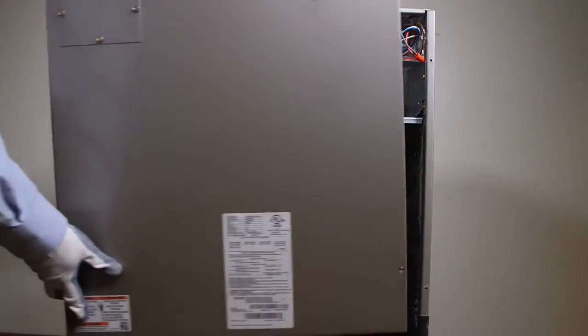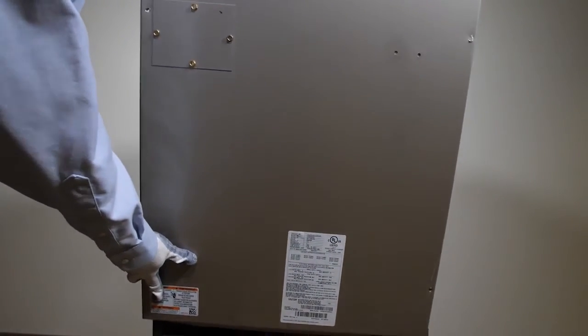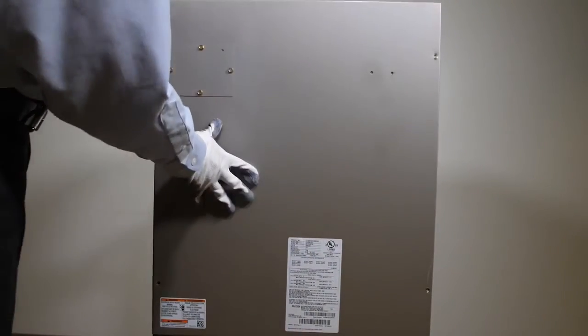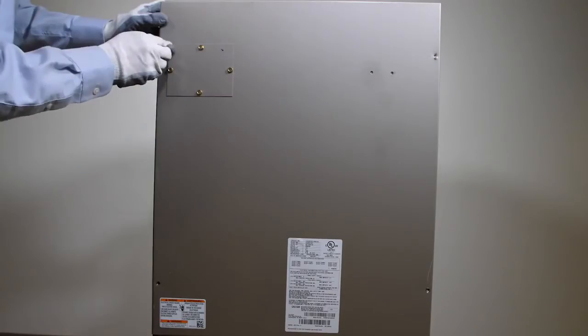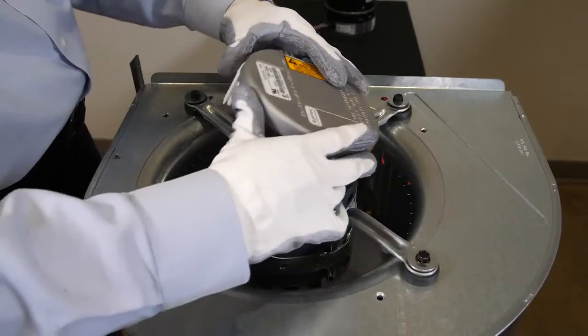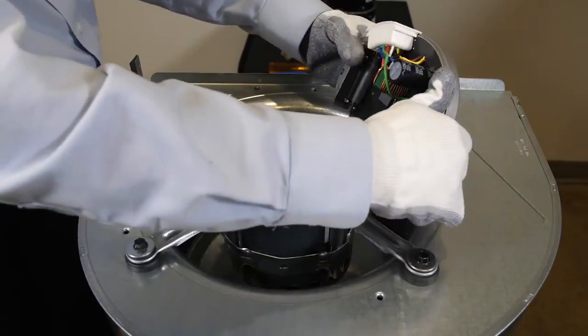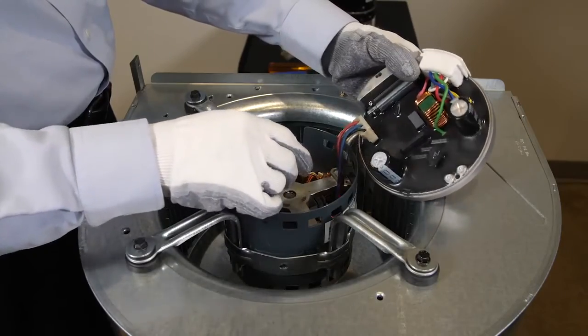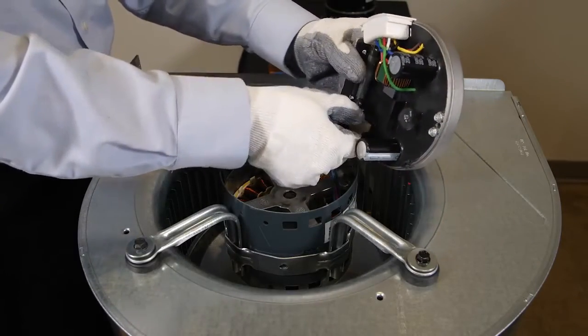Replace the access panel. Reconnect line voltage to the unit and verify that the blower is operating properly. In summary, when troubleshooting fan motors, don't always assume that it's necessary to replace the entire motor. The problem may simply be the control module, and switching out the module is quick and easy.